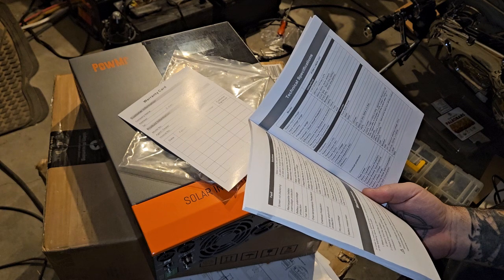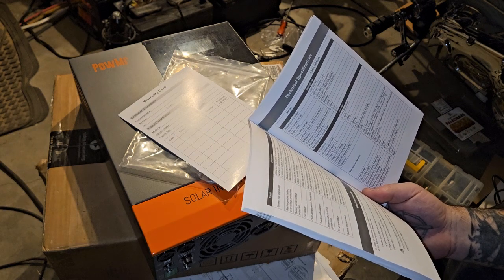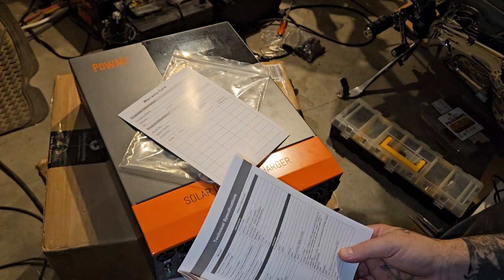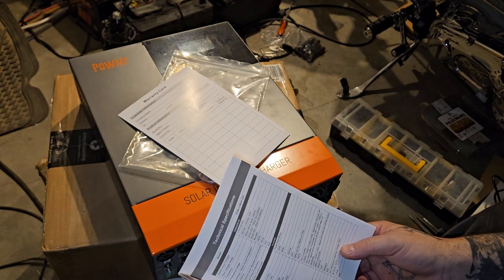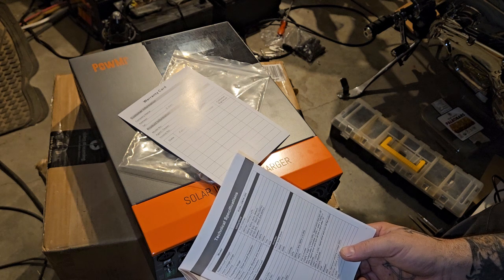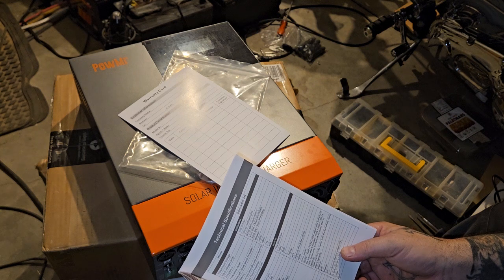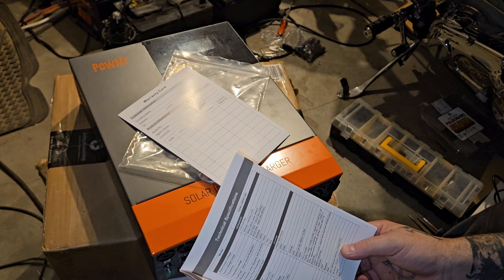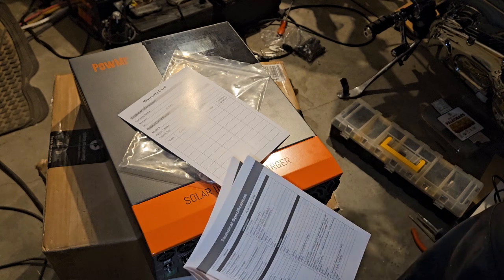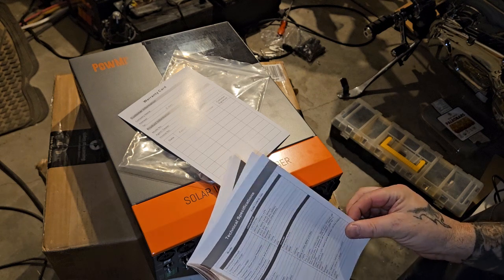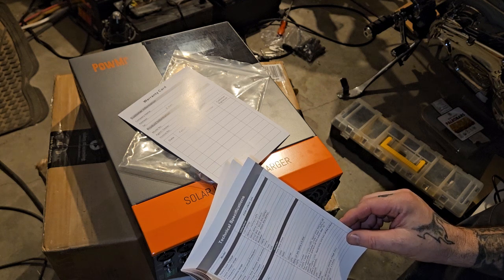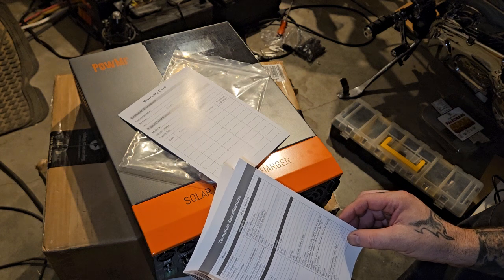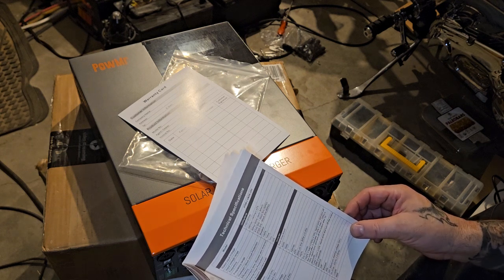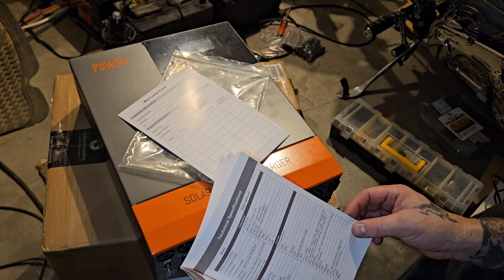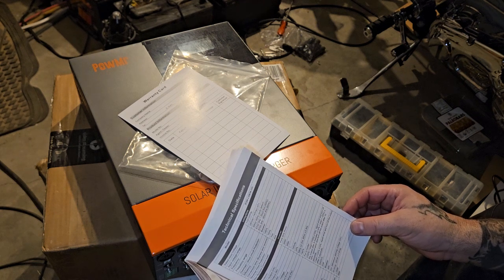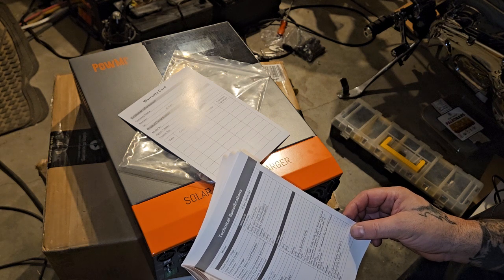Efficiency 92%. Overload protection: less than 102% load, less than 110%, plus or minus. Report error and turn the output off after 5 minutes of 110% or 125%, plus or minus 10%. So I think it'll run at 102 to 110% load, but if you go over 110 to 125, after 5 minutes it will shut itself down to protect itself. Load 125% plus or minus, report error and turn off output. Peak power 4500 volt-amps.